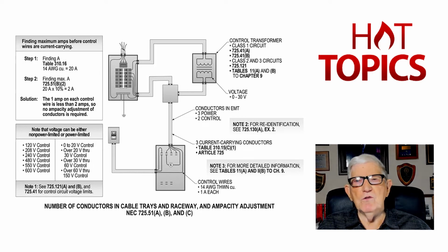But now notice the class 2 circuit is outlined in the blue typing, and you go to 70E Article 100, Electrical Hazard, and that defines it as a class 2 circuit, not harmful to you because the energy output is limited, see. But a class 1 and 3, that's not always true, as you see in that illustration. If you look at the illustration at the left, at the very bottom, you notice that a class 3 can operate at 60 volts all the way up to 150 volts. They can be a shock hazard. In some cases, might even be an electrical arc hazard to you, see.